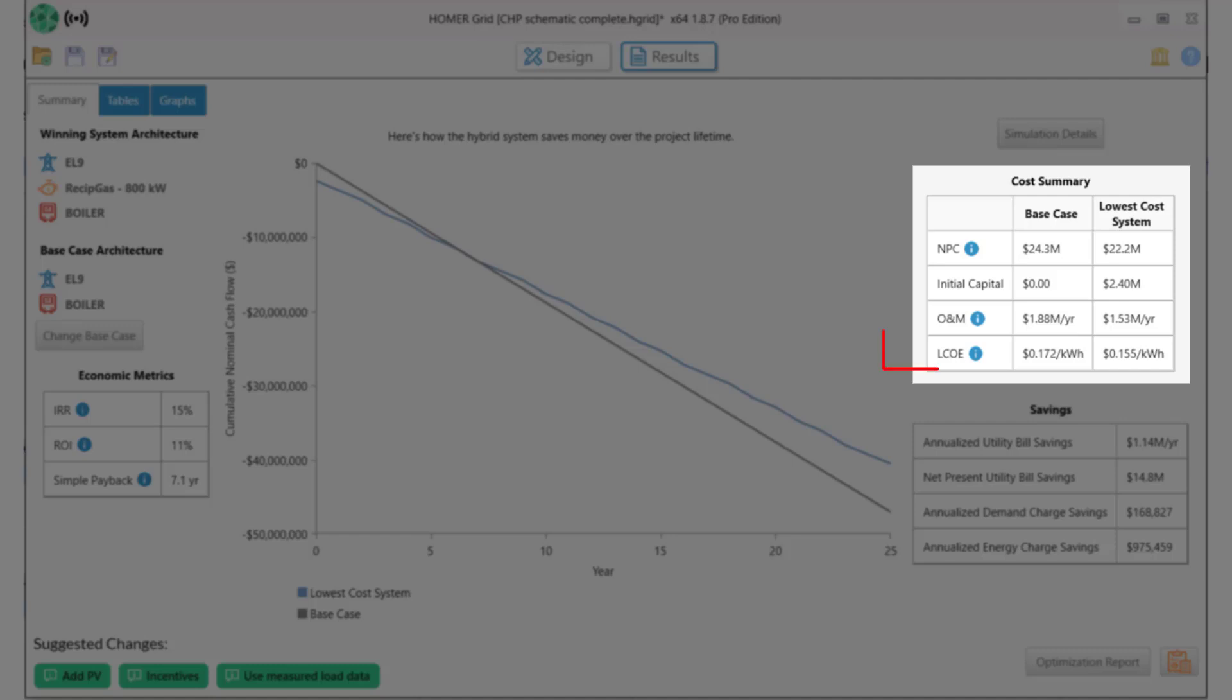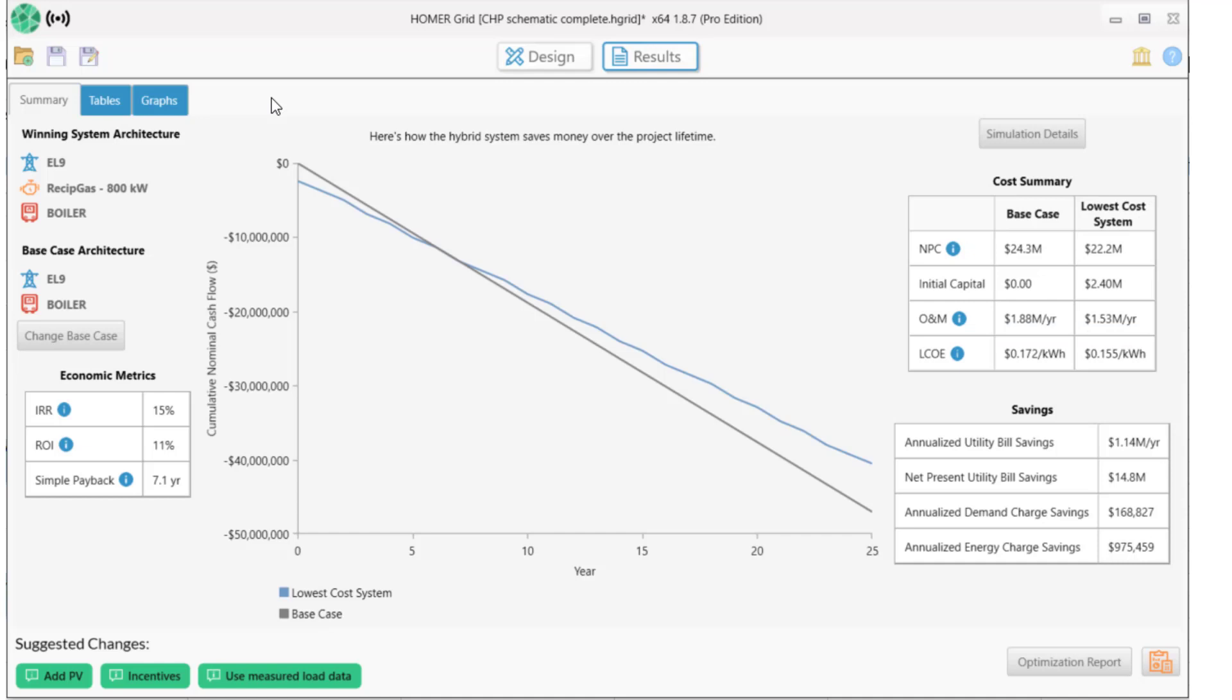The levelized cost of energy for the CHP system is 15.5 cents per kilowatt hour versus 17.2 cents for the base case system. This is a very compelling result with a strong economic basis.